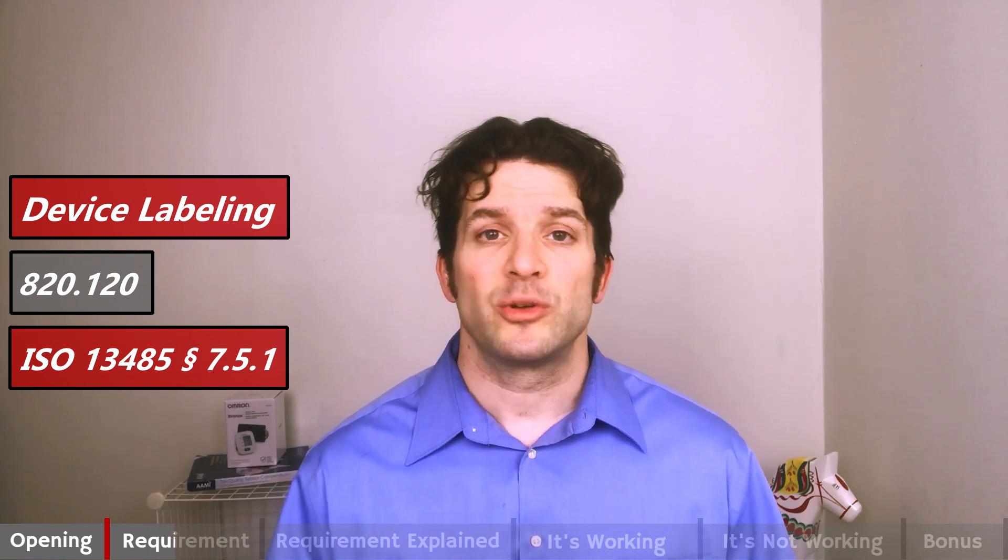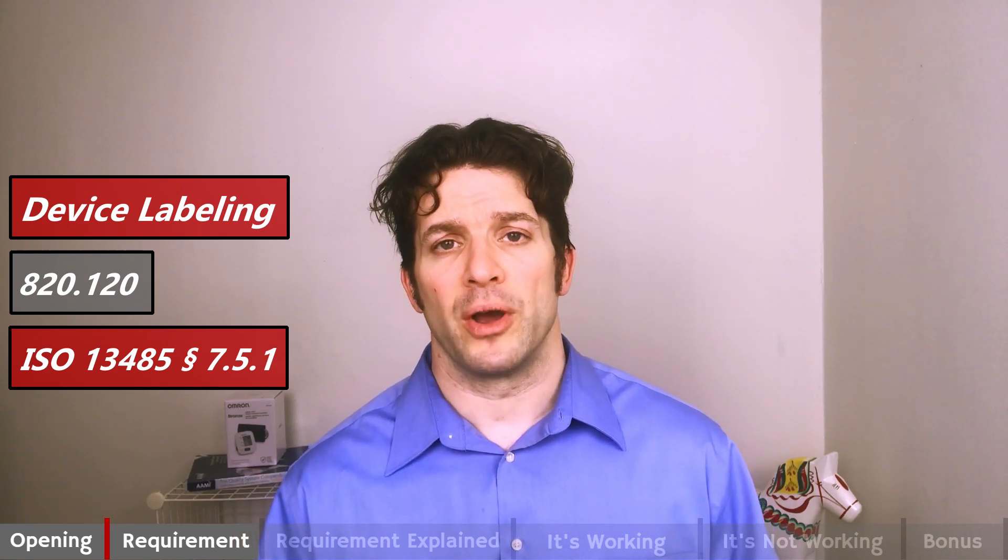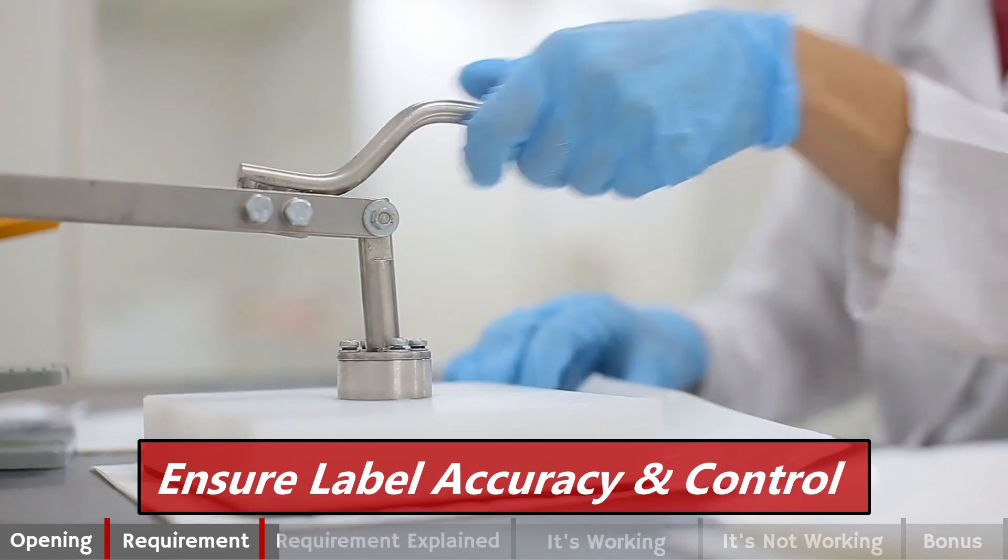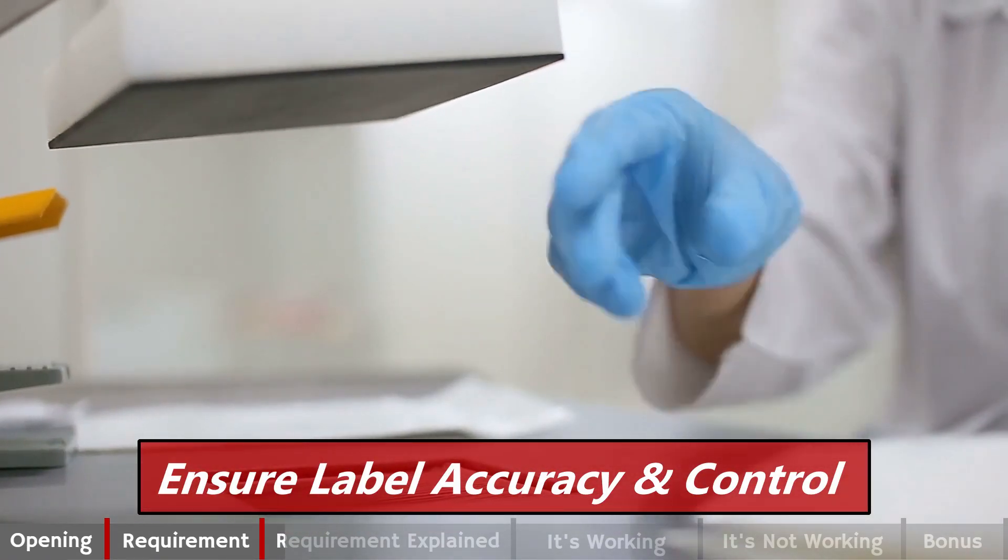Our requirement, device labeling, comes directly from 820.120 and 13485 section 7.5.1. Device labeling in five words: ensure label accuracy and control.